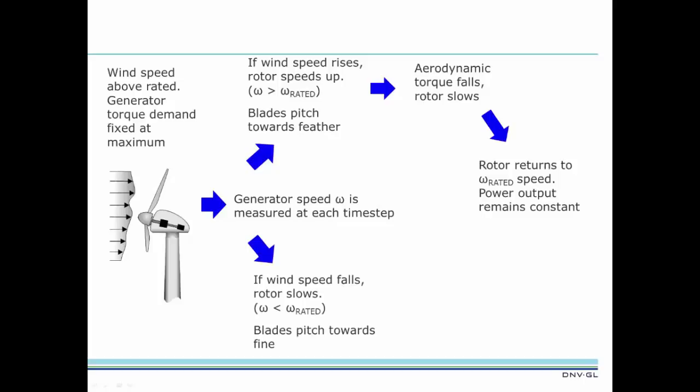Similarly, if wind speed falls and the rotor begins to slow down, the blades are pitched closer to fine pitch. This increases the aerodynamic torque, and the rotor speeds up. The rotor returns to rated rotor speed, again restoring constant power output.